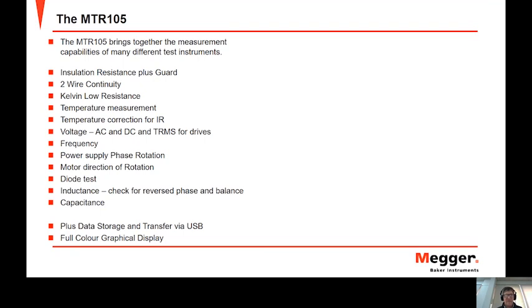So the MTR105 standard features include an insulation resistance test, which includes the guard feature, for those that know guard. We have a 2-wire continuity test, a Kelvin low resistance test down to 1 milliohm, that's a 4-wire measurement. We have a temperature measurement via a Cat2 600 volt type T thermocouple, which is included. And this allows for the temperature correction of the IR test that we spoke about. We have a voltage measurement function, both AC and DC up to 1000 volts, and also true RMS measurement for inverter drives.